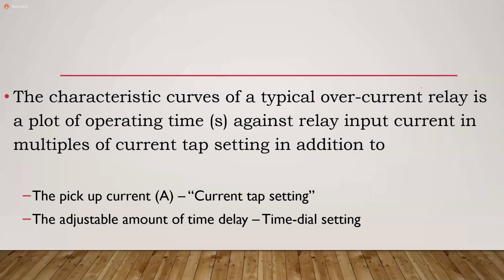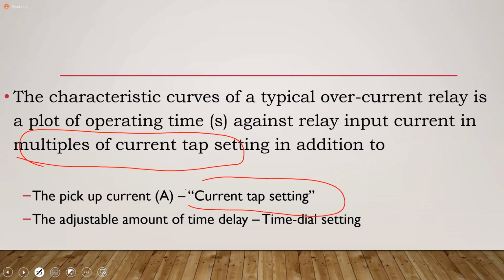So we have some characteristic curves, and it's a plot of the operating time against the relay input. And this relay input is in multiples of tap. There's also the current tap setting and the time dial setting. Remember that thing that I showed you that you have to turn to determine how fast the relay operates. The lower the number, the faster it will operate. So for the same current, if I have it on time dial 1, it will operate much faster than if I had it on time dial 5. So the lower the time dial, the faster the operation.